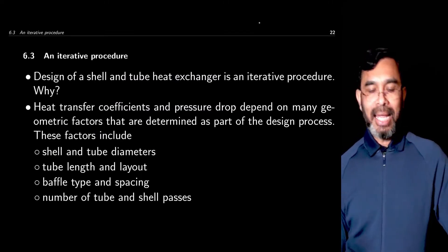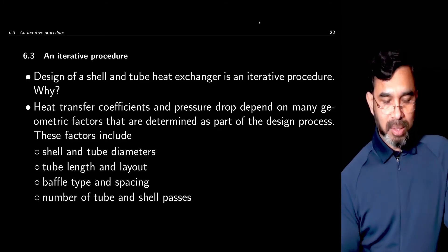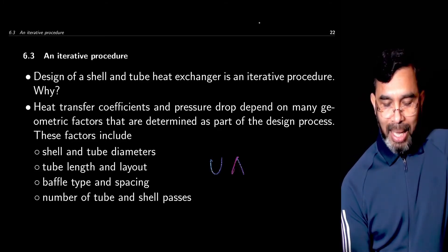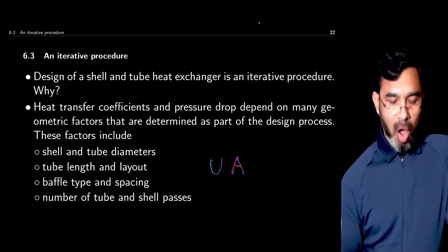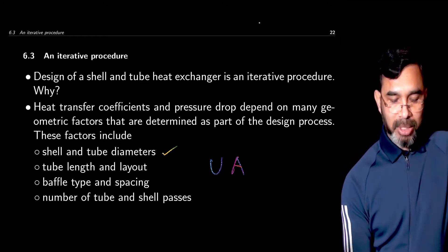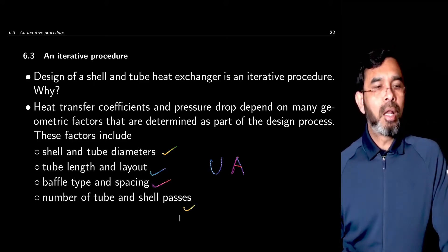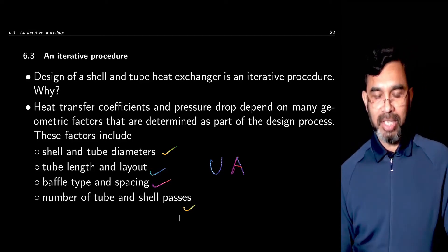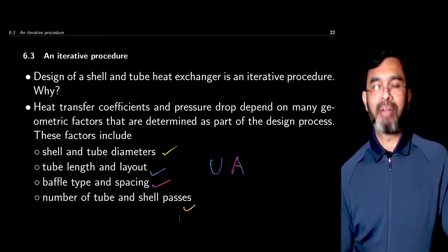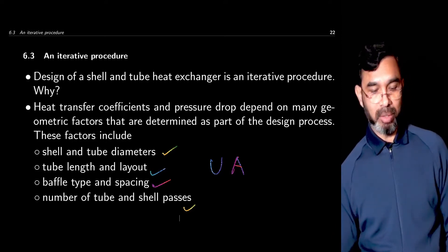The design of a heat exchanger becomes an iterative procedure because we have U and A — these two parameters — and both of them depend on the shell and tube diameter, their layout, length, baffle type, and the number of shell and tube passes. All of these design parameters affect the heat transfer area as well as the heat transfer coefficient by affecting the flow properties of the fluids. That's why it becomes an iterative procedure.